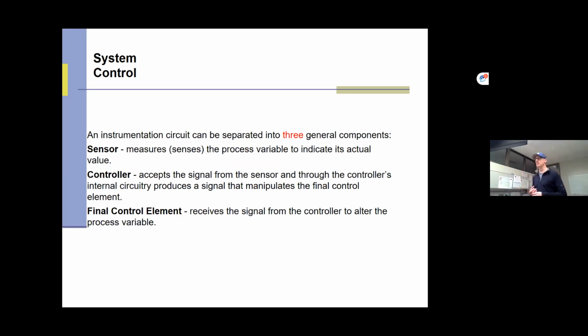It accepts the signal from that transmitter. It says, hey, I'm going to use that signal, and there's some equations and logic put in there by your instrumentation folk, and it will send out a signal to the final control element, or in this case, that was that pump. It receives a signal from the PLC and says, okay, I'm supposed to do this, right? And again, it's just sending a milliamp signal, and that's all it's doing. The brain is in the PLC. So it's super important for you guys to make sure that your PLC is programmed correctly, protected, especially from power outages, and that you have some spares.